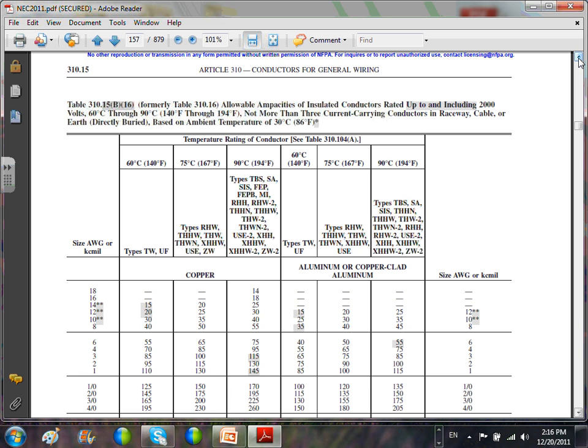For example, suppose I have a motor, and my motor is 10 amps, right? A 10 amp motor, 3-phase, 10 amp motor. Motors are a continuous load, so you have to multiply it by 1.25.